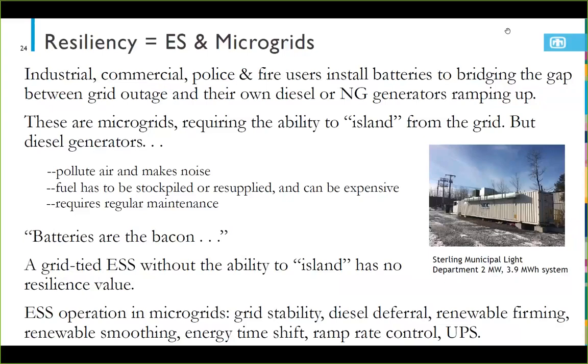So talking about these natural gas or especially these diesel generators, they're very effective for short-term or even long-term resiliency, but they have problems. They make noise, they pollute the air, you have to stockpile the fuel, and it can go bad over time. These generators take regular maintenance.